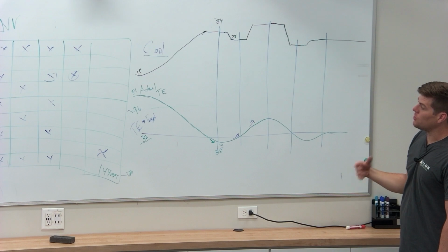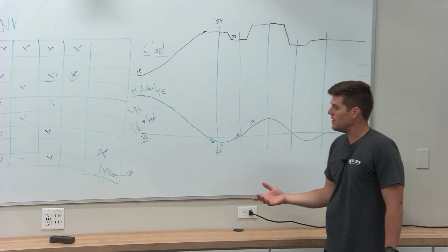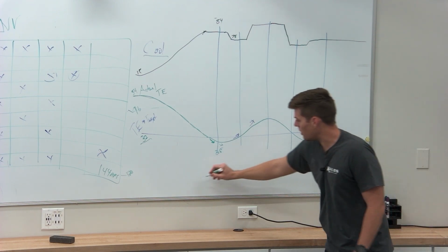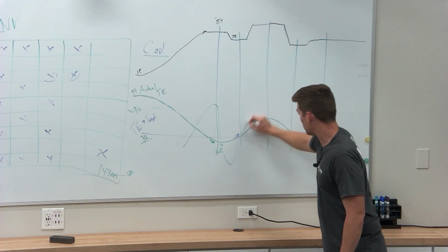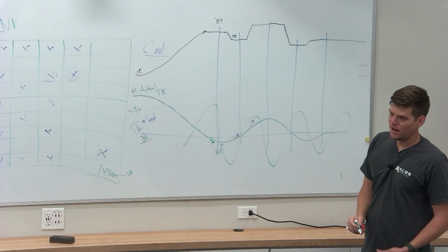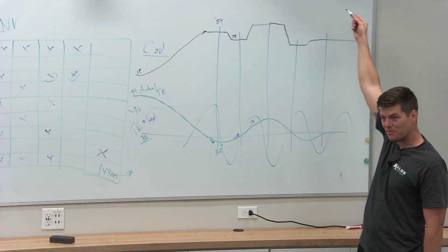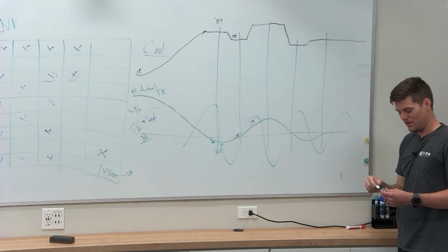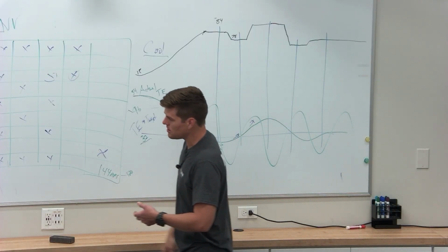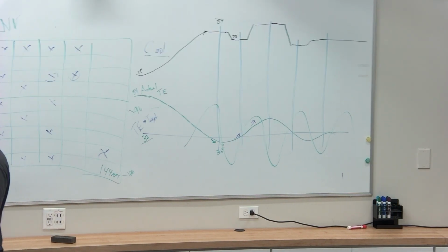Service Checker data where you'll instantly see there's a problem is where it looks like a heart rate monitor, where this line is always like this. And the compressor speeds do the same thing. Compressor speeds are up, down, up, down, up, down, fast, slow, fast, slow, fast, slow, right? Those are problems within the system. There's supposed to be small, gradual changes when the charge is correct, when there's no restrictions in the system, when all the valves are doing what they're supposed to be doing, and they're modulating the way that they're supposed to.